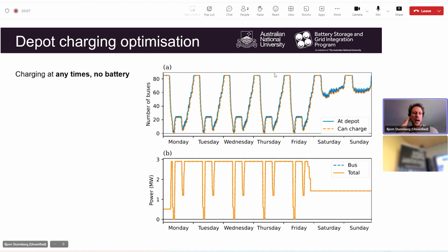In the bottom graph, you see the power loads of charging this fleet of buses. There are roughly 80, a bit more than 80 buses required to service the schedule for these 18 routes in Belconnen. RouteZero optimizes the charging to minimize the peak load placed on the grid, so you see a pretty flat, about 3 megawatts of power being pulled throughout the weekdays, which drops at moments where a lot of the buses are out on the road, and drops again over the weekend where there are many fewer scheduled trips, so you can charge the buses at a much slower pace.